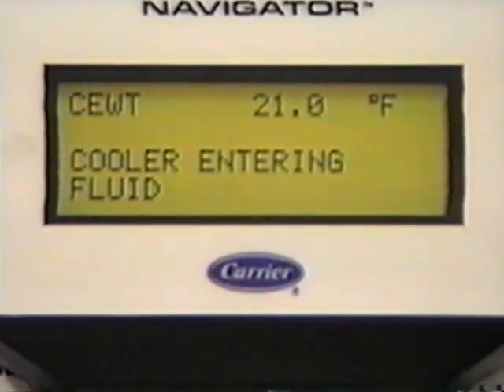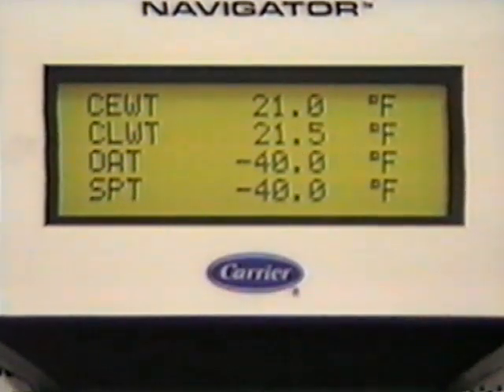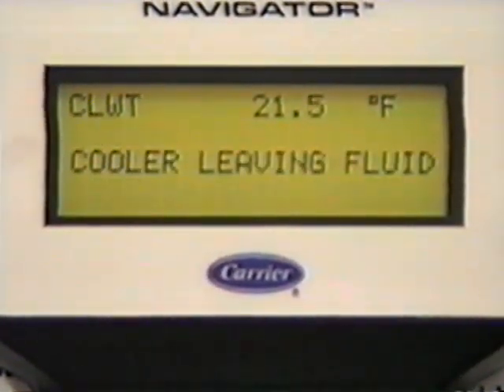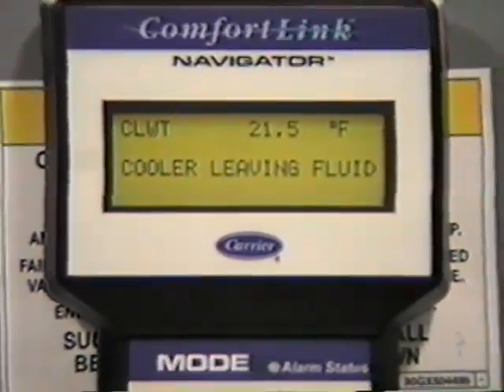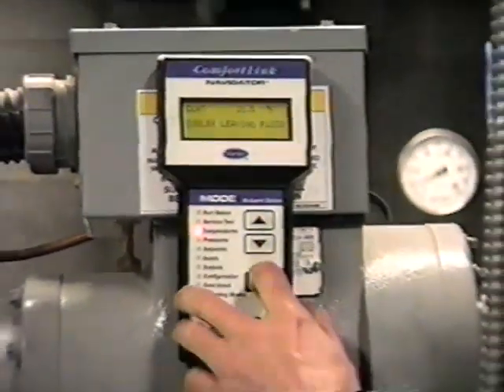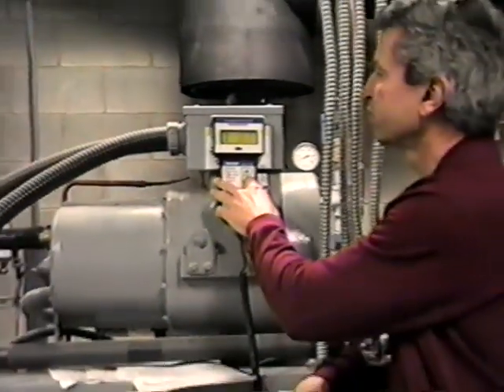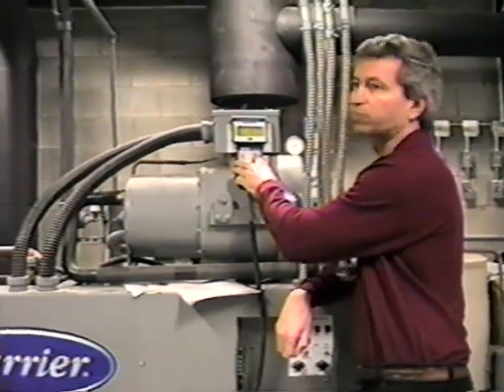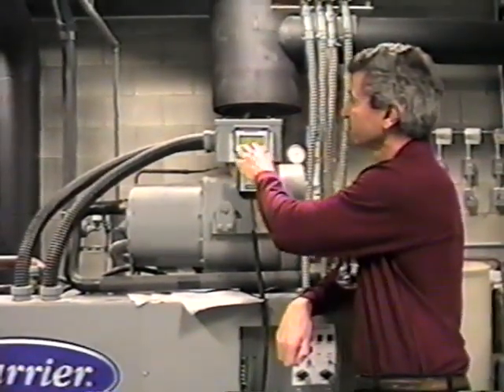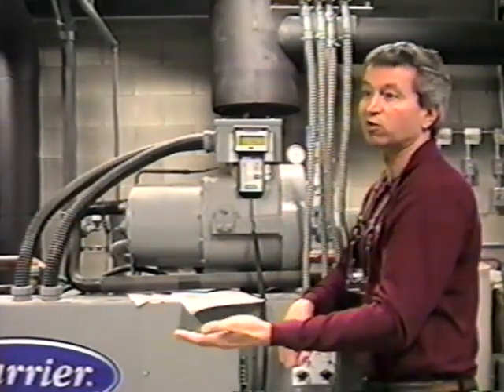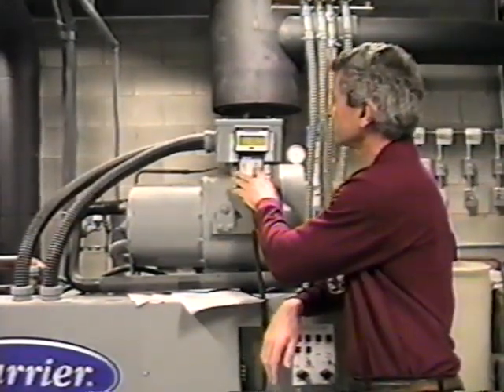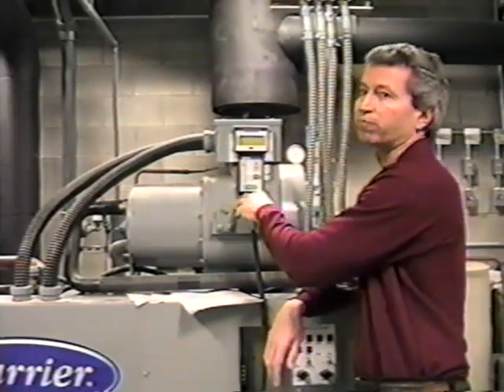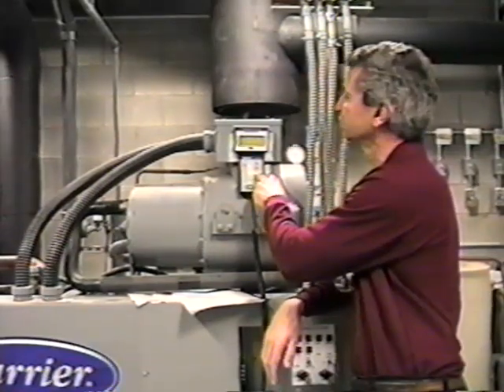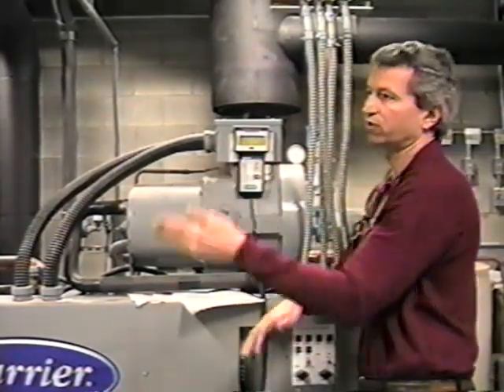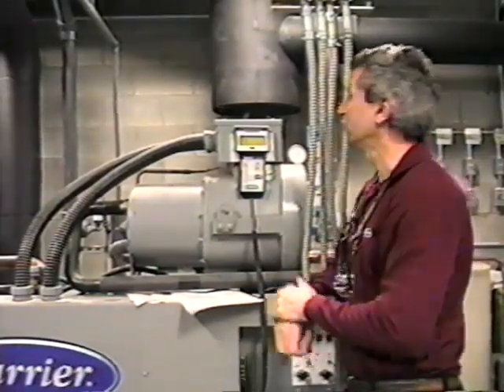Okay, so CEWT is cooler entering fluid, and then we hit escape and scroll down. And again, the abbreviations are on that sheet, so you can either refer to that or expand it on here. And these other temperatures that are on this particular screen aren't being used, so you'll see a blinking -40. Essentially that means nothing's plugged into it, so it's not being utilized. So essentially you just have two temperatures on that screen that are going to be of any meaning to you. Okay, and like I said, circuit A and circuit B are just mirror images of one another, just the different circuit temperatures.